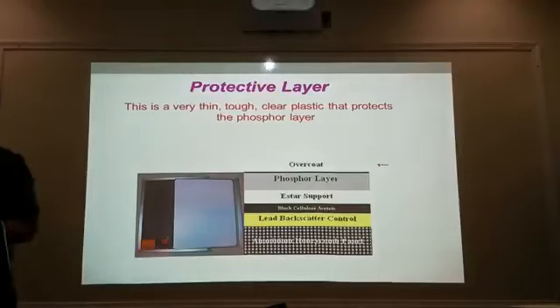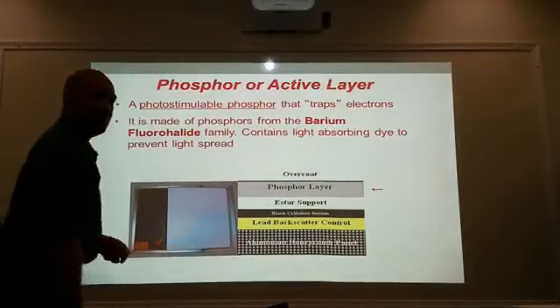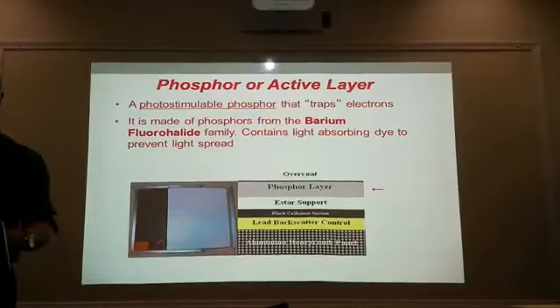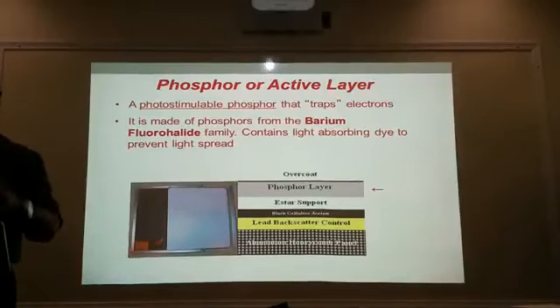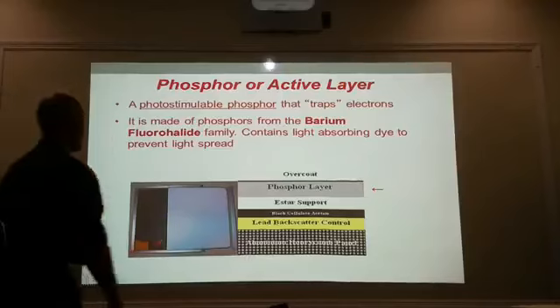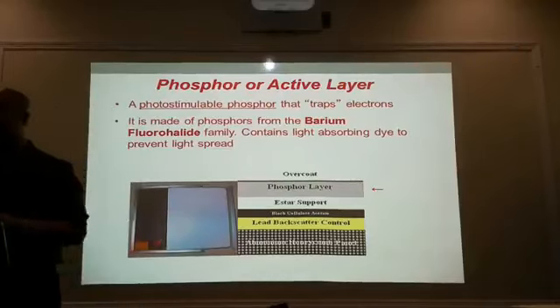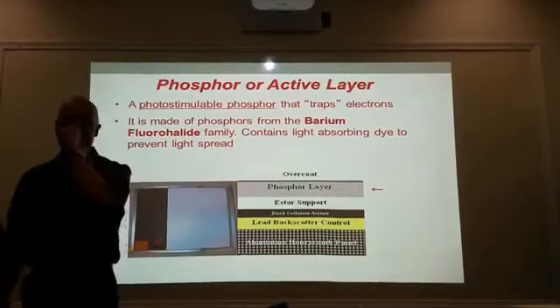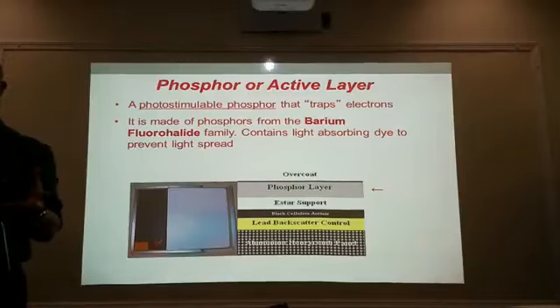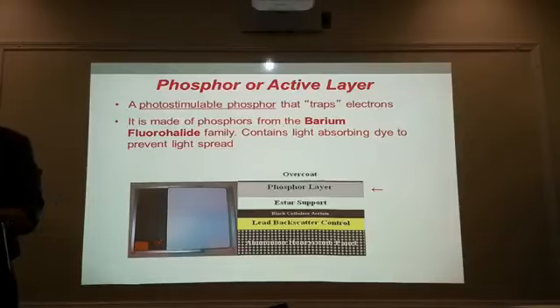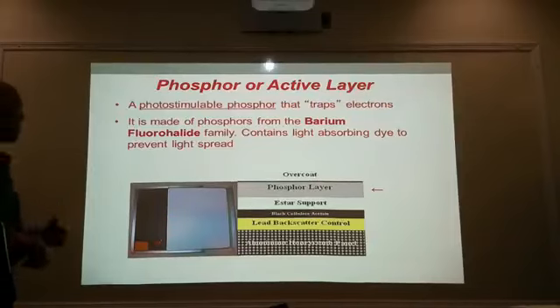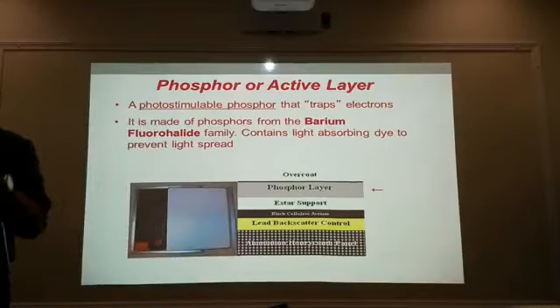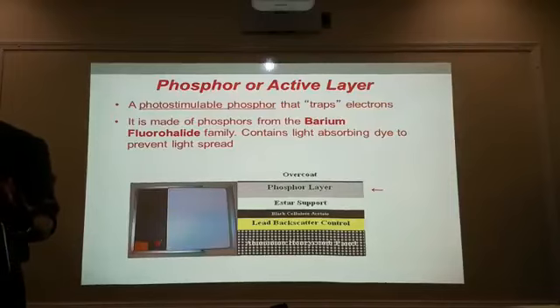The active layer contains the phosphors — the barium fluorohalide. The barium fluorohalide also contains a light-absorbing dye to prevent light spread, which means we can control the diffusion of the light, which controls the speed of the screen. If it has a light-absorbing dye, it makes the detail better — it slows it down a little bit, but insignificantly.